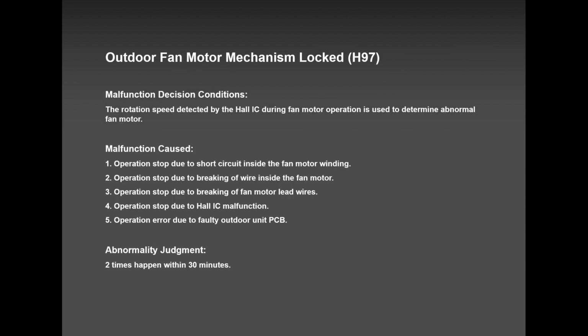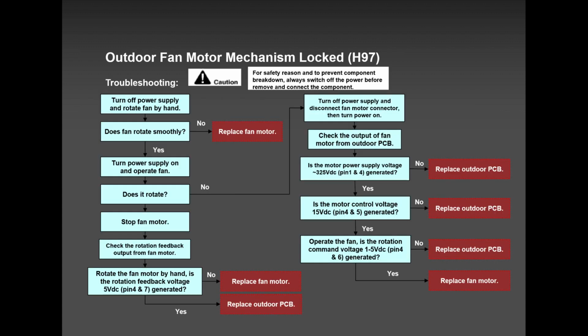H97, very popular in winter time. Every winter, I get 1 or 2 phone calls. And when they go out and look at the unit, one guy called me and said he can't find the unit because it was covered with snow. And 1 or 2 guys called me and said the fan blade was frozen, stuck. They cleared the ice, they cleared the snow, everything up and running. And 1 or 2 guys that called me, obviously the fan motor was defective, they replaced it, up and running.